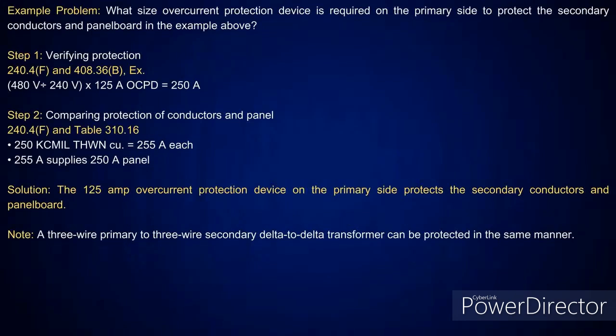Now, looking at this one, what size overcurrent device is required on the primary side to protect the conductors and panel board? We had an example we were showing here, but this is very simple. I'm showing a transformer here with a 480 volt primary, 240 volt secondary, and a 125 amp overcurrent device upstream. We were just showing how to do this calculation, and that gives you 250 amps. So I was going to size the conductors to protect the secondary conductors and the panel board it was going down to. If I had 250 amps, what's the next size above that? That's 255 amps in table 310.16 in the 75 degrees C column, which would have required a 250 kcmil conductor to supply that panel board.